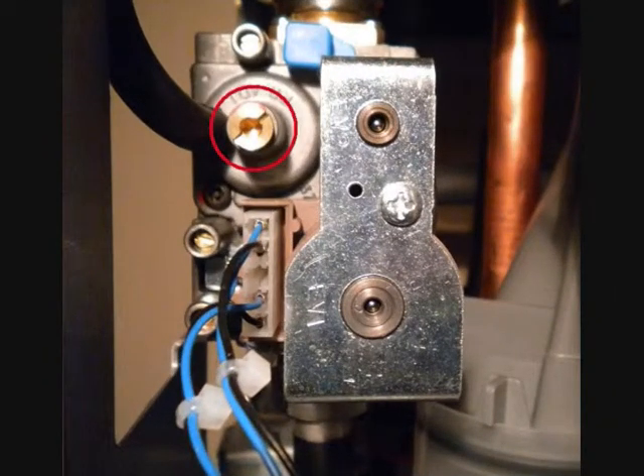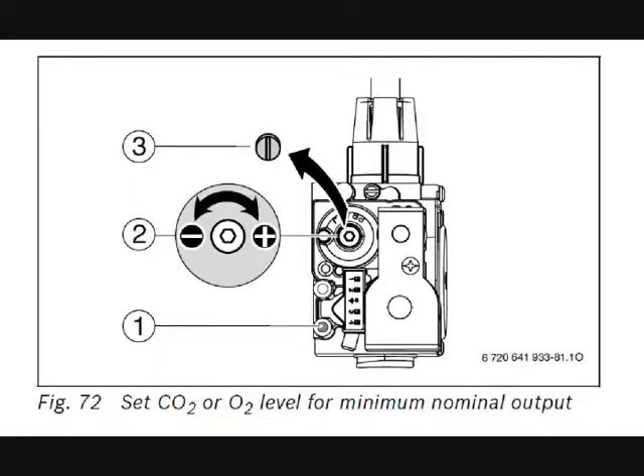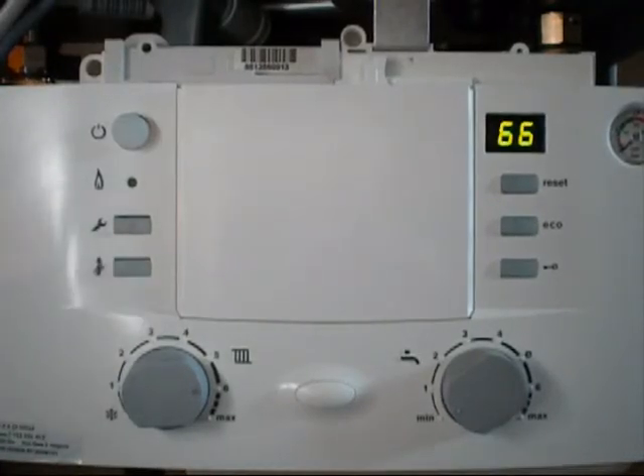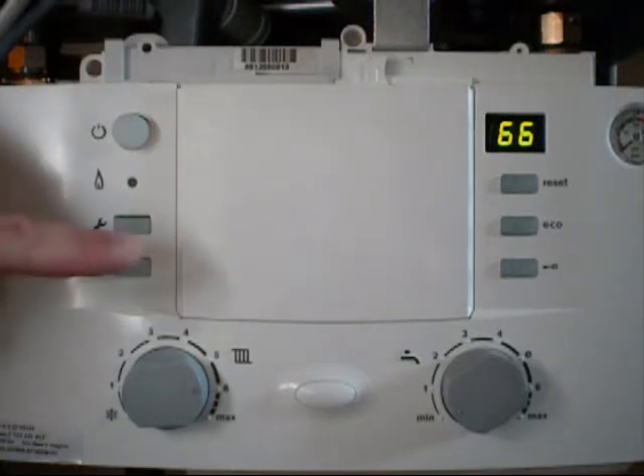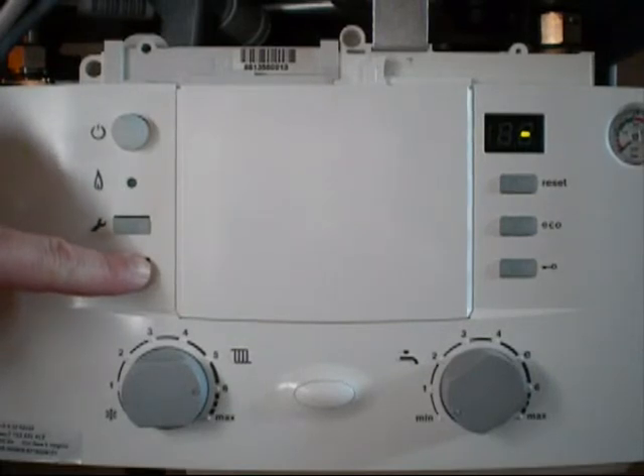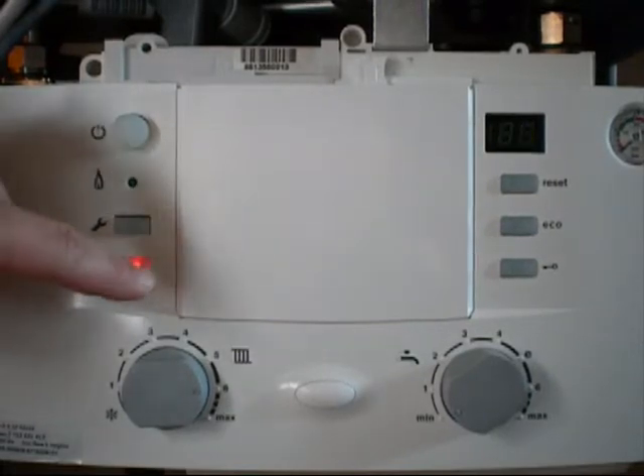If adjustment is necessary, remove the sealed brass screw from the gas valve. Using an Allen wrench, make very slight adjustments as necessary. Clockwise adjustments increase the CO2 level, whereas counterclockwise decrease the CO2 level. Press the chimney sweep button again to return to normal operation. It is best practice to recheck your high fire CO2 reading if any adjustments to the low fire setting have been made.